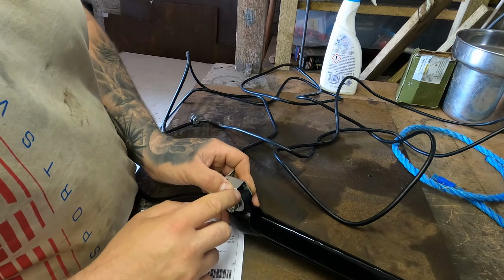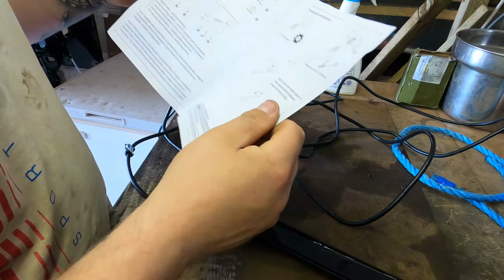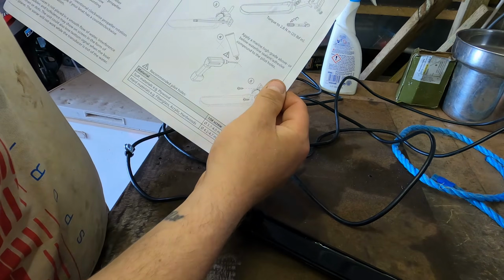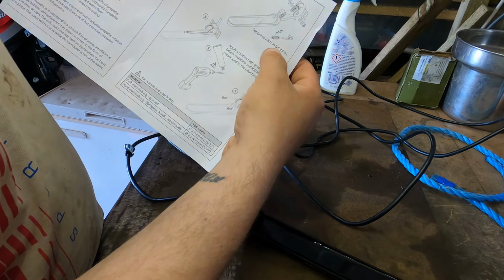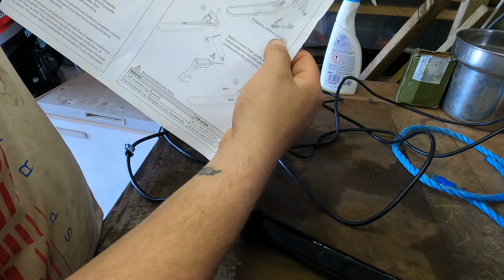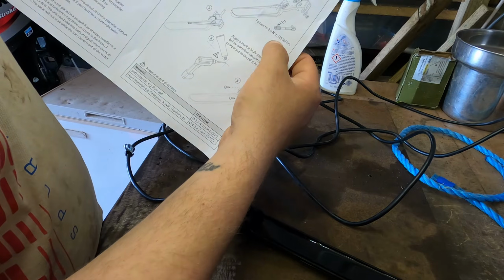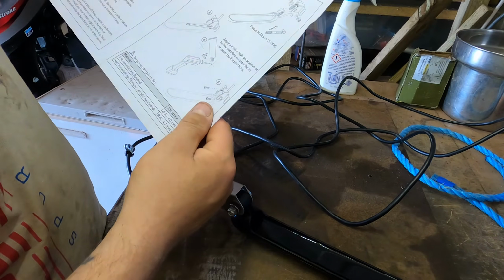This nut does not need to be tight at all. The instructions say 2.8 Newton meters of torque, or 25 pound-inch. If you do it too tight, you won't be able to lift up and drop down the transducer.